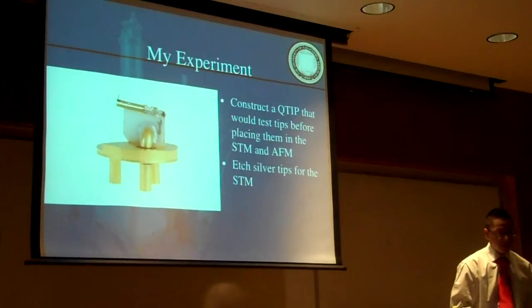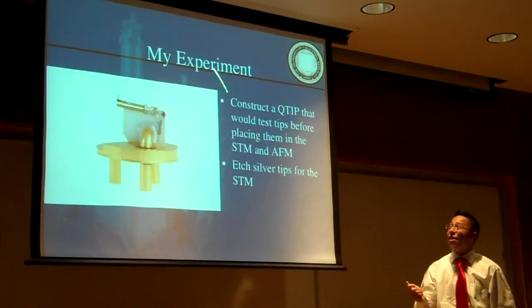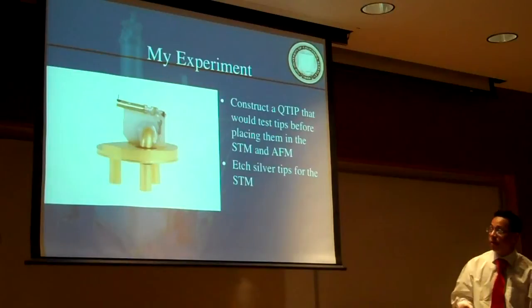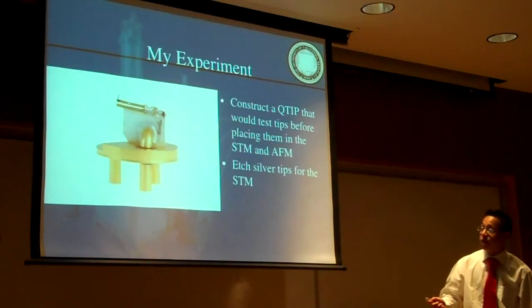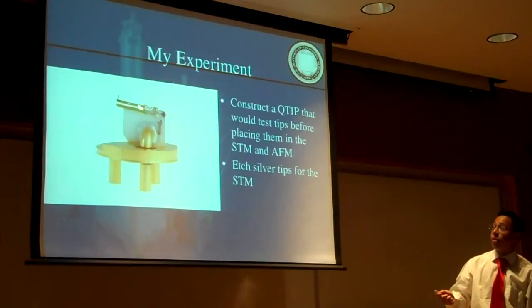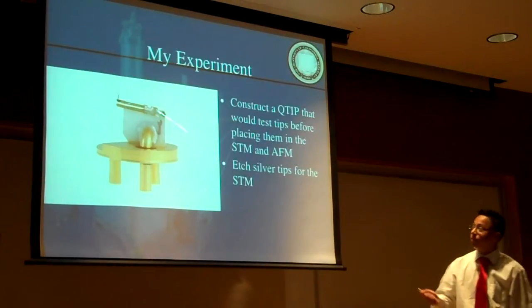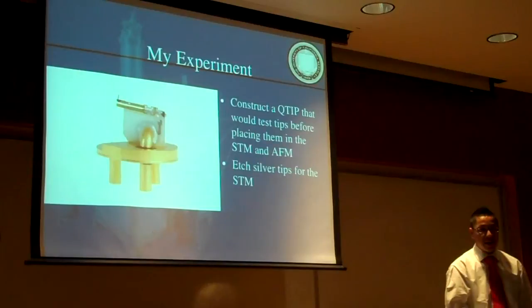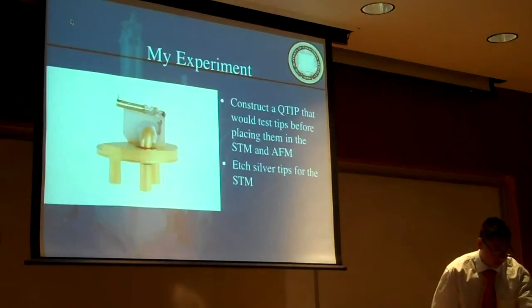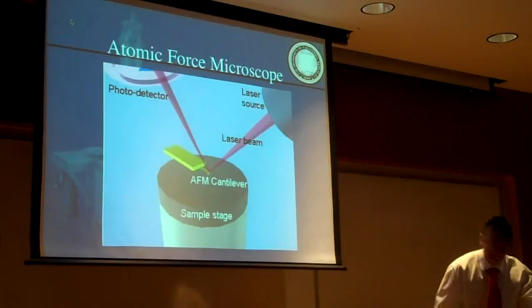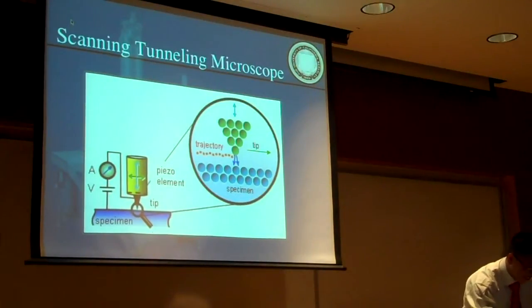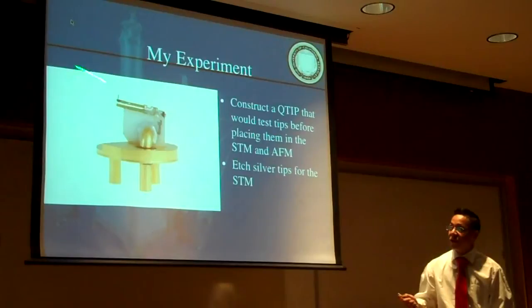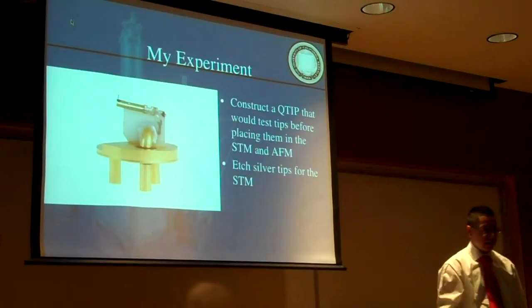My experiment: I told you about STM and AFM. What I did was construct a Q-tip tester that would test tips before placing them in an STM and AFM. Here we have a Q-plus sensor. As you can see, we have our little tip and our piezoelectric material — the quartz tuning fork. We etched silver tips for the STM. Our AFM is different from the general one because we don't use a laser. Instead, we use the piezo, which detects the deflection by electricity.